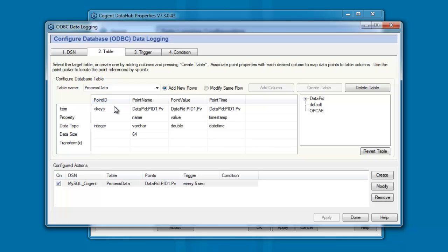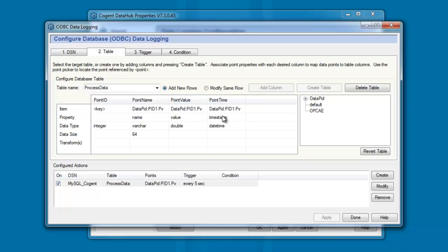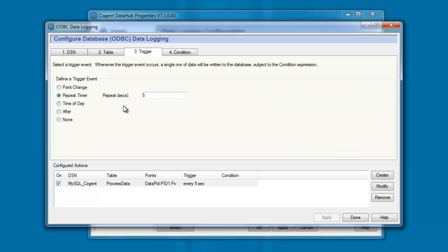Each of the rows has a first column which is labeled PointID. And this is a key field. It's an incrementing integer number. The second column is the PointName, and we're just taking the Name property from the DataPoint. The third column is the PointValue. And the fourth column is the PointTime, or the timestamp on the data change. And we are triggering that every five seconds.